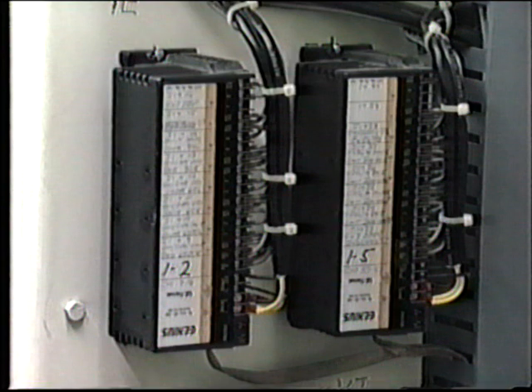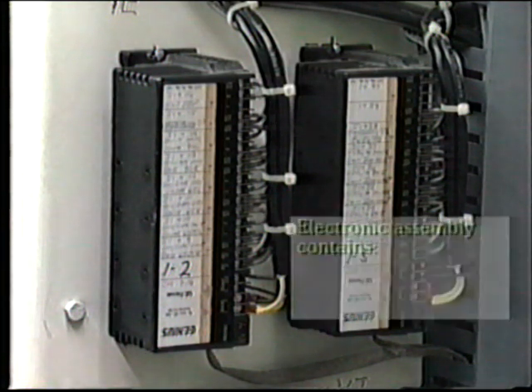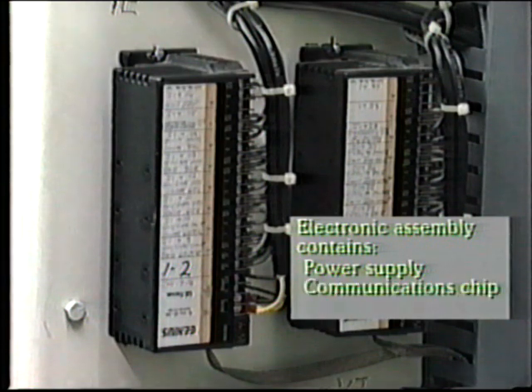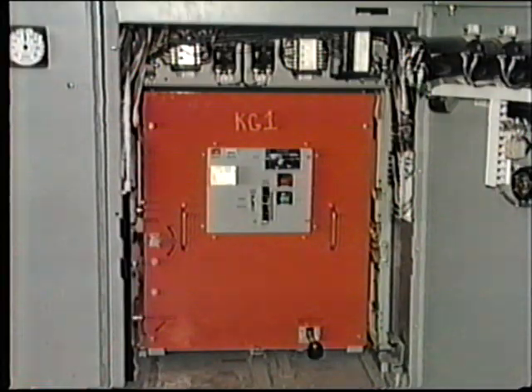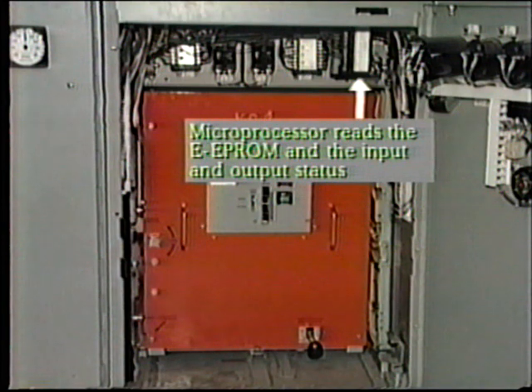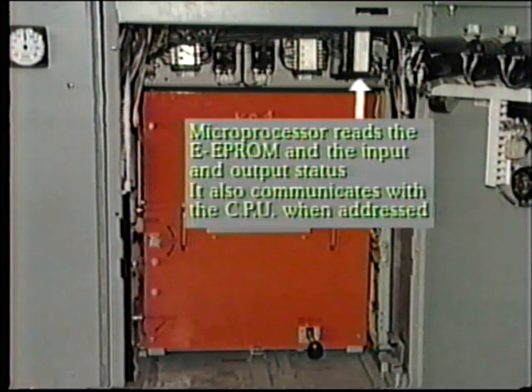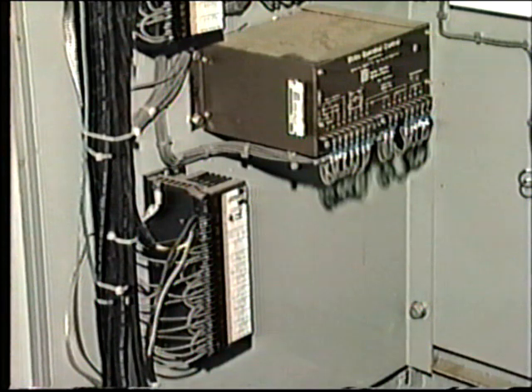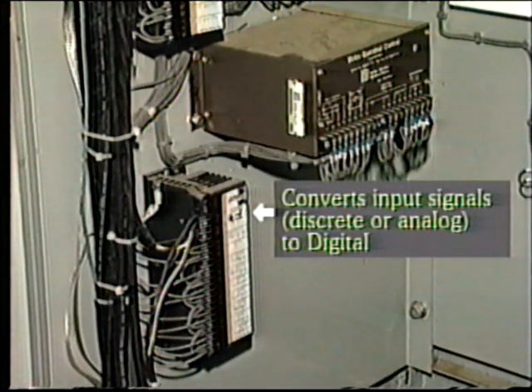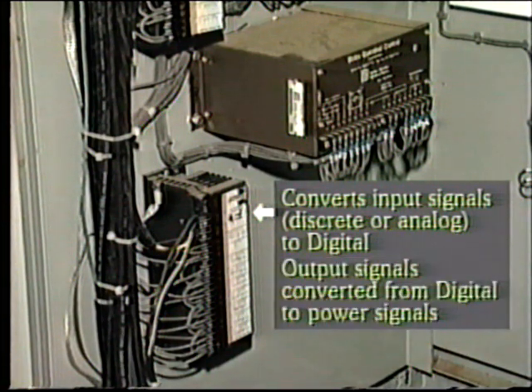The electronic assembly is also contained in the I/O block. This contains the power supply, the communications chip, the microprocessor, and other electronic components. In operation, the microprocessor reads the EEPROM and the input and output status. It also communicates information to and from the CPU when addressed. The I/O block performs the useful function of converting input signals, whether they be discrete or analog signals, into digital form for efficient and rapid communication. Similarly, the output signals are converted from digital signals to power signals, which may be discrete or analog.